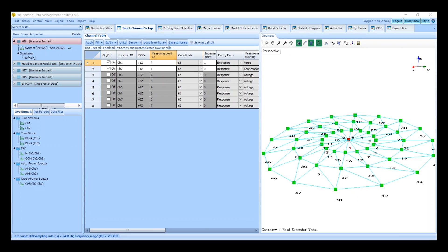We will be changing the point of impact by one measurement point so we need to configure our excitation channel to have one increment point. The increment point refers to how many points will be incremented for each test run. The increment point is set to zero for our response channel and one for our excitation channel.